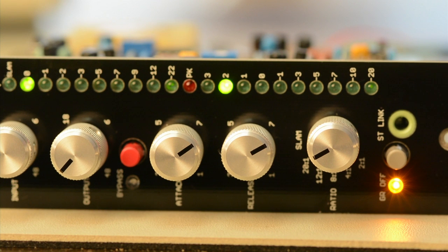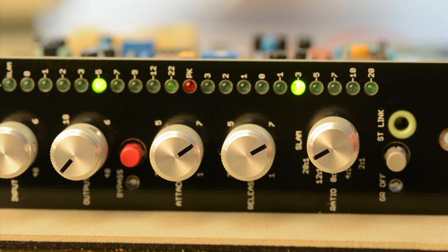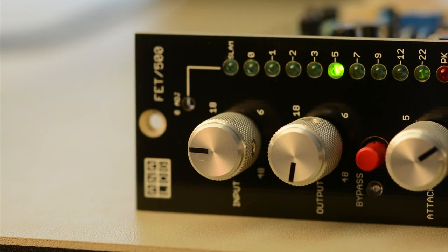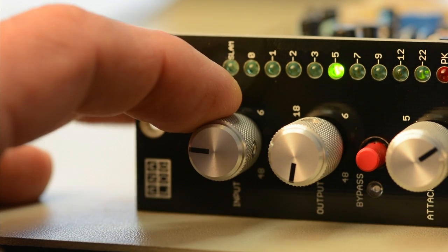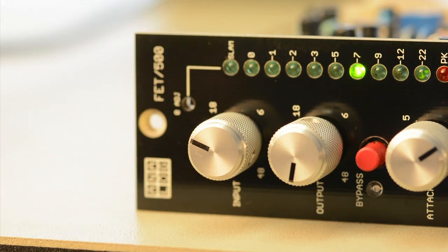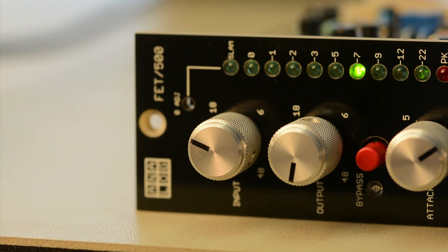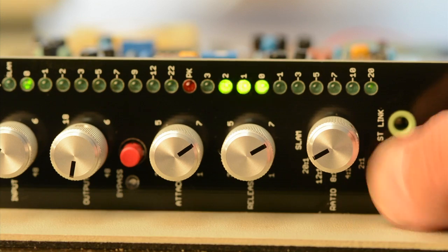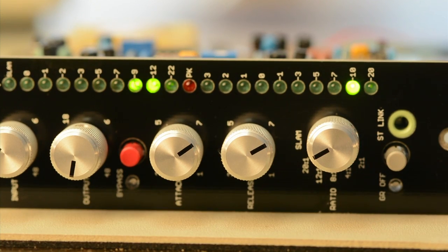Activate the gain reduction by releasing the push button and observe the drop in the output. -7 indicates a 9 dB drop from +2. If it falls short of -7 dB, turn the input knob up. If the meter drops more than minus 7 dB, turn the input knob down.